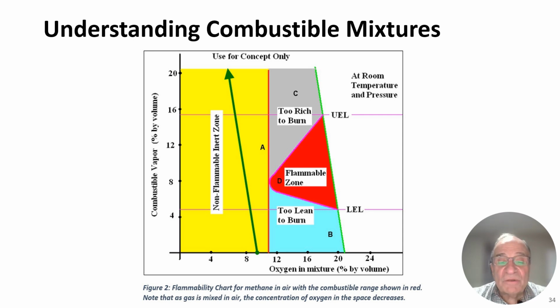If I start off with a vessel that's been purged and there's only 9% oxygen in the room and I start to add gas, what happens is I never go into that flammable range. So this zone here has been purged out sufficiently, so I never go into a flammable range. Now, when you're dealing with piping and you purge out piping, you typically bring the piping all the way down to almost 0% oxygen because it's very easy to purge out a pipe. You put nitrogen in one end, stuff that comes out the other end is originally 100%. Let's say you had gas in that pipe, 100% gas, or you had air in the pipe, and then all of a sudden your oxygen content in the pipe drops from 16 to 12%, 8, 4, almost zero, down to what is essentially zero, and you say, okay, that pipe is purged. And that's easy to do with a pipe, especially a small pipe.